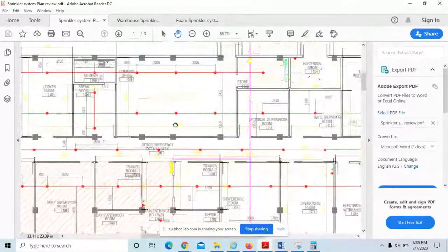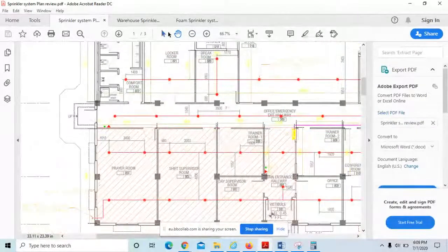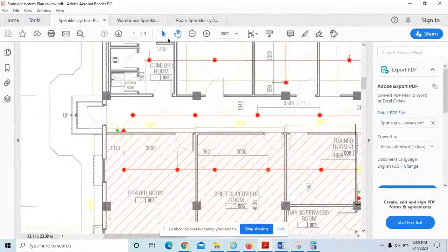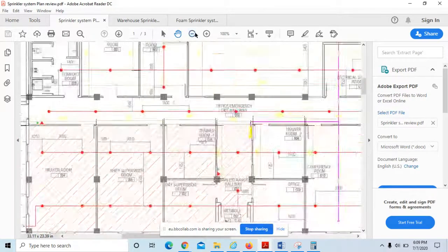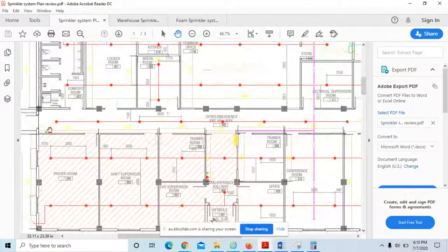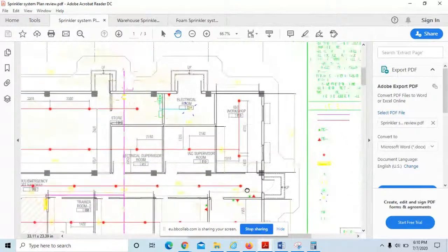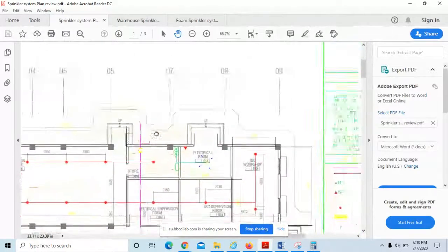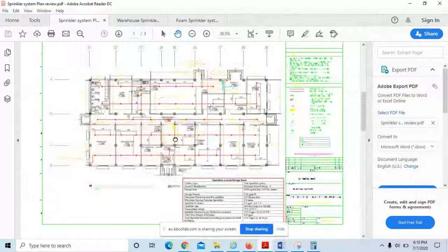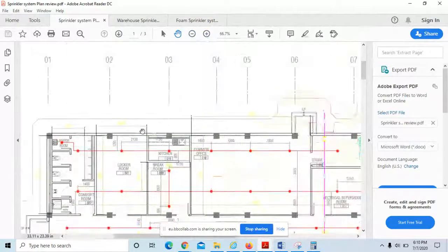Now we have to make sure what the maximum distance is between two portable fire extinguishers. As we discussed for fire extinguishers in fire protection 2, the maximum distance is around 75 feet for class A hazard, and the office comes under that. In this case, we have one extinguisher at one entrance and the other at the last one. We have to make sure the maximum distance between these two shall not be more than 75 feet, because this office area must be ordinary hazard, right?